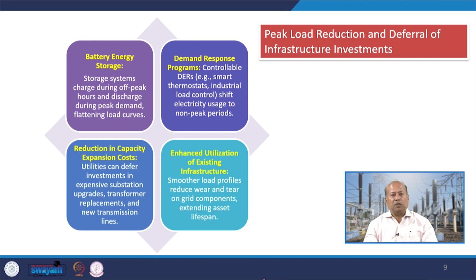So, what we need to do, the distribution company, the DISCOM, has to replace most of their old transformers or replace the substations or put in an additional transformer to cater to the new customers or consumers. And can we avoid such investment due to DR integration becomes a question. So, battery energy storage system. Storage systems charge during off peak hours and discharge during peak demand, which helps the load curve to be flattened. So, that means the peak valley can now be reduced a little bit due to battery energy storage.